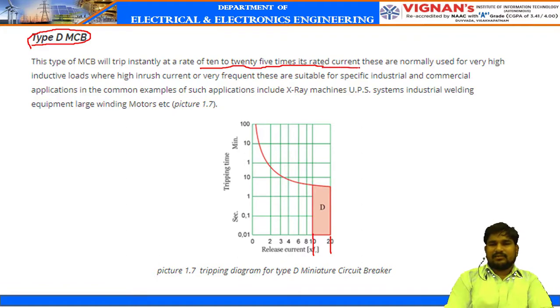So this can be used for very high inductive loads. It will be used for high inductive loads where there are high inrush currents or very frequent switching, suitable for specific industrial loads and commercial applications. Like X-ray machines, UPS systems, industrial welding, or large winding motors. For this protection, type D MCB will be used.